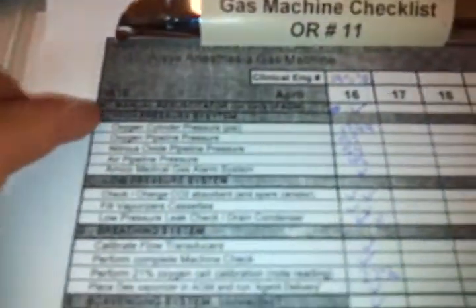Okay, so we're going to look at the sheet for a second. Basically, it's going to go over the high pressure systems. So that's the high pressure system is basically the oxygen tank. So we checked it in the back. All the information will come up right here. So the tank, the PSI is 1353, 1348 in between there. So you want it above 1,000. If it goes below 1,000, you have to switch. And that just gives you the pressures for the lines coming from the wall. So oxygen 55, nitrous 55, air 49. And you have to record them all on here.